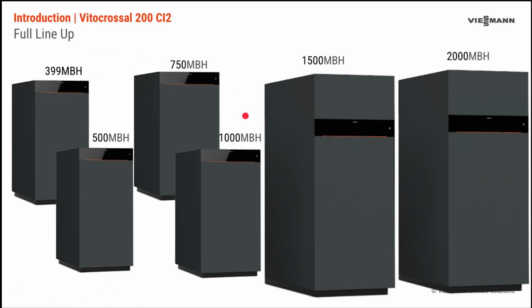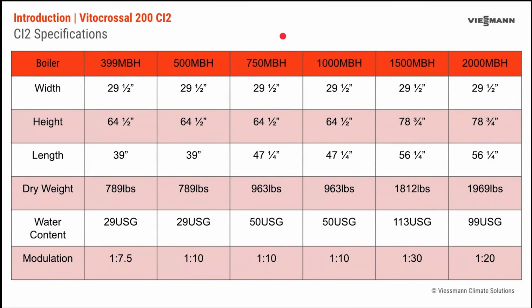750,000 BTUs, 1 million BTUs, 1.5 million BTUs, and 2 million BTUs. A quick glance at some specifications, the 6 boilers across the family. We won't go over all of the dimensions, but we focus in here on the width. So the width remains 29.5 inches across the entire family of boilers. And that's an important dimension because it allows us to roll the boiler through any standard doorway.